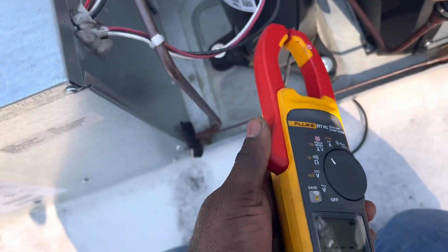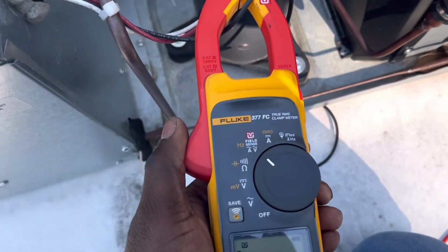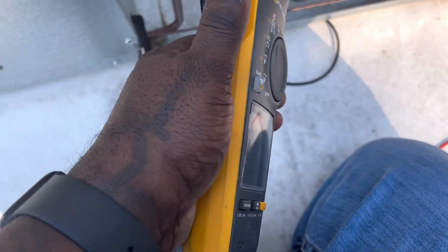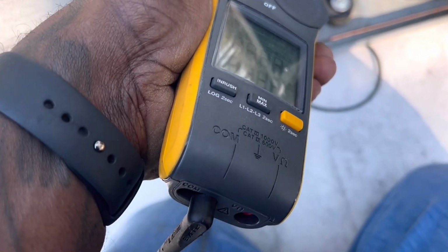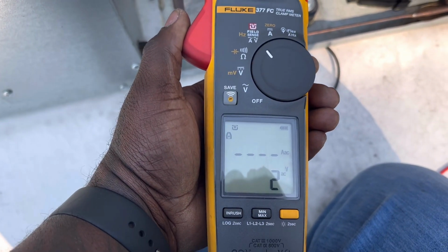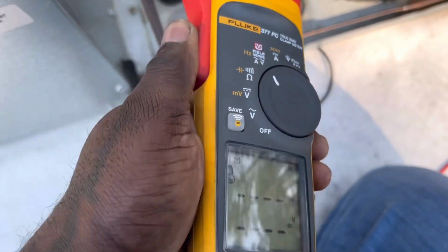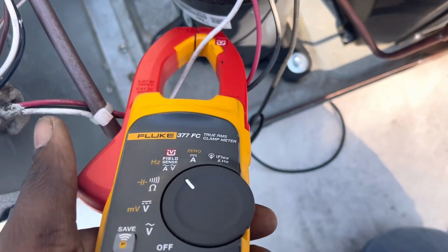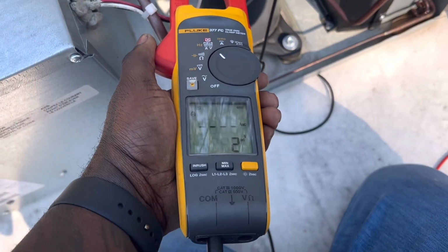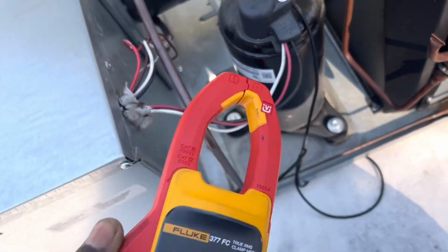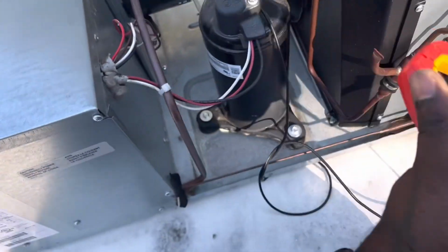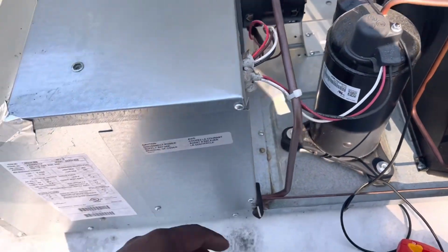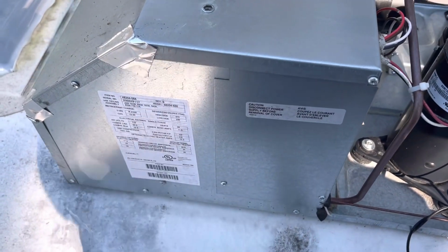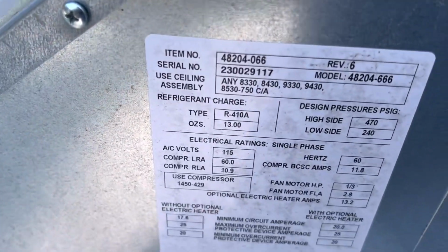And I'll go back to my compressor wires. Nothing on the black. Nothing on the red. Nothing on the white. So that run capacitor, I'm having an issue with it. So let me take this apart and see what we got going on. Here's the sticker.